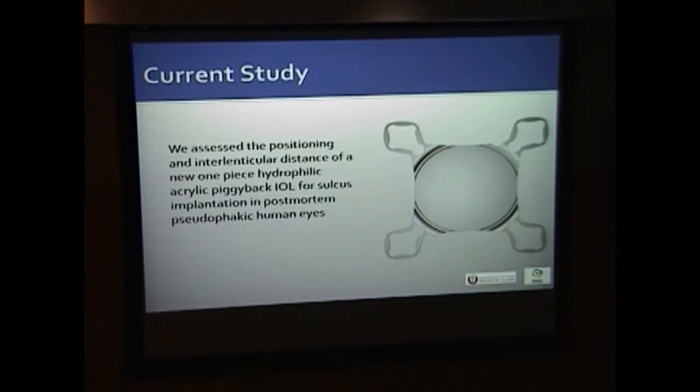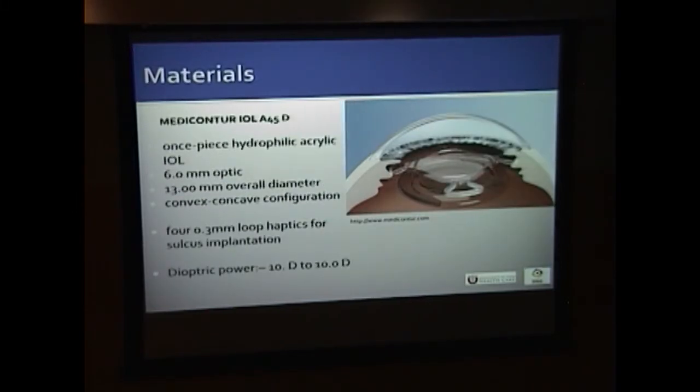We performed a study on 12 cadaver eyes that had primary IOLs already in place pre-mortem. Our study lens — the MediContur — has a similar square design to the 1stQ Add-On. It is a one-piece hydrophilic acrylic, with the same large dimensions as the other market lenses, and features four flexible loop haptics that can accommodate different sulcus sizes.